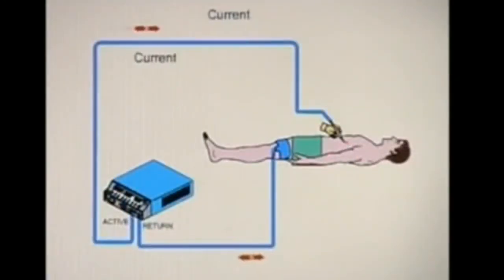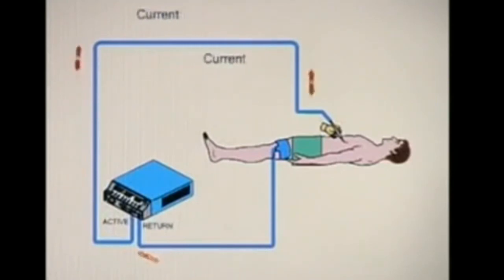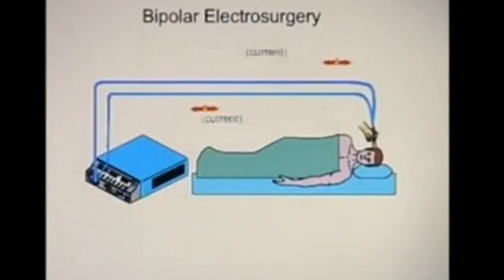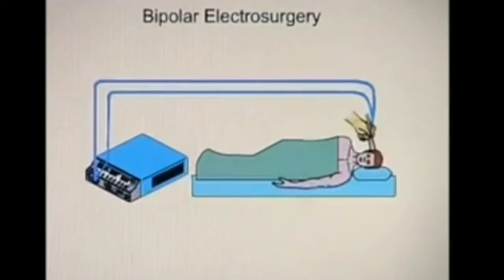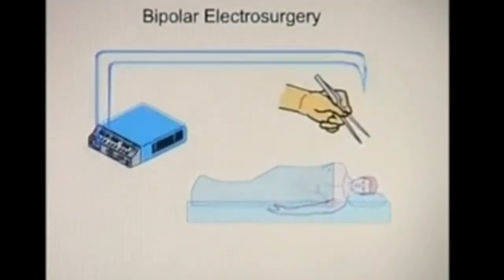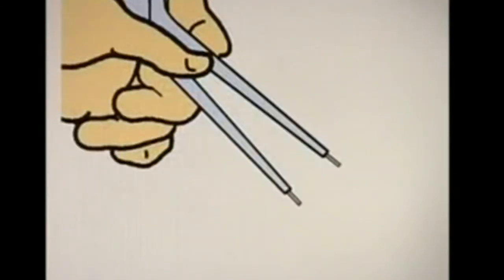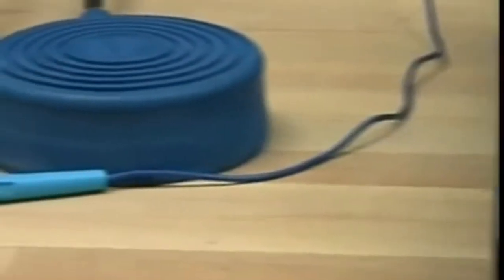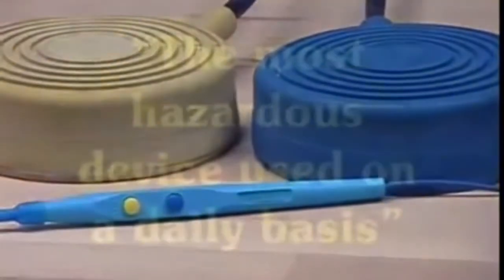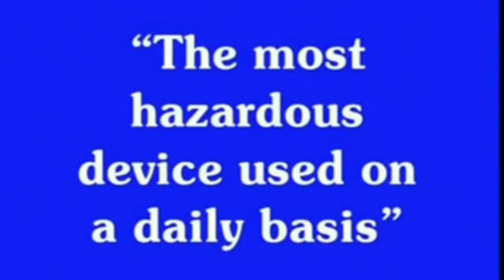Monopolar electrosurgery requires a patient return electrode and uses the patient as part of the circuit. Bipolar electrosurgery does not require a patient return electrode and restricts the flow of current to between the tips of the bipolar forceps or similar instrument. And finally, don't forget that the electrosurgical generator has been described as the most hazardous device used in the operating theatre on a daily basis.